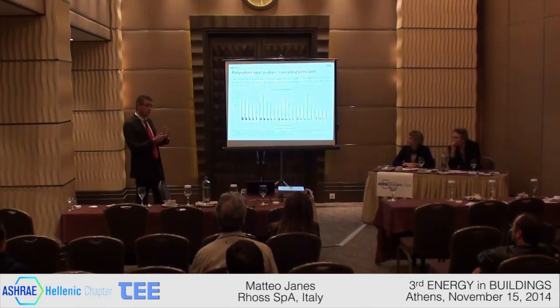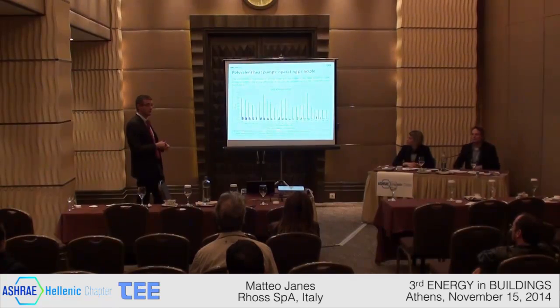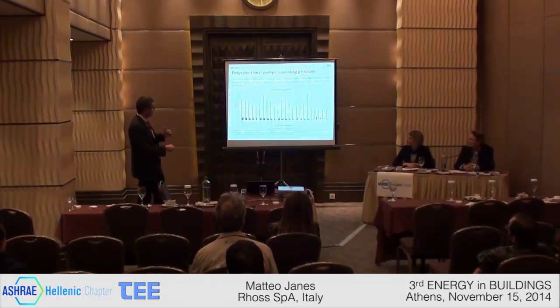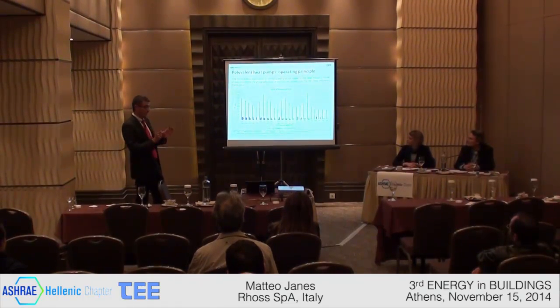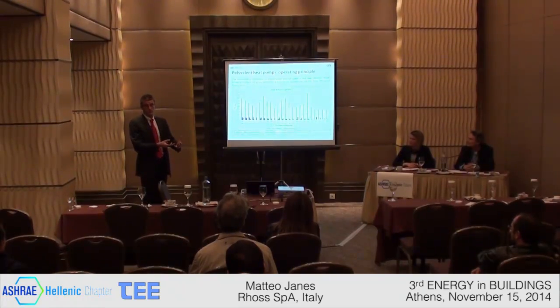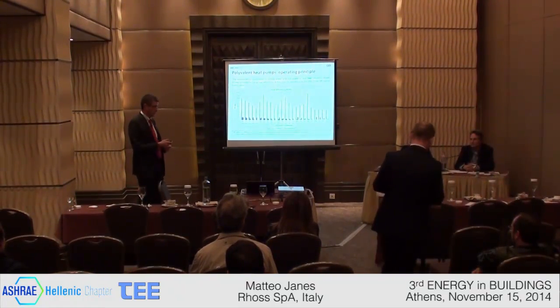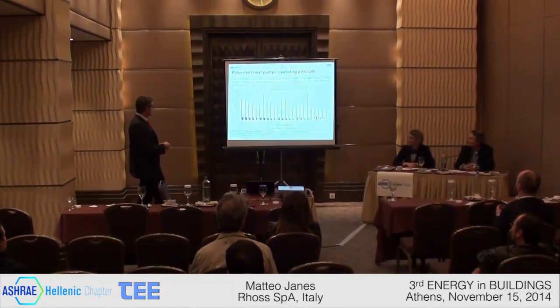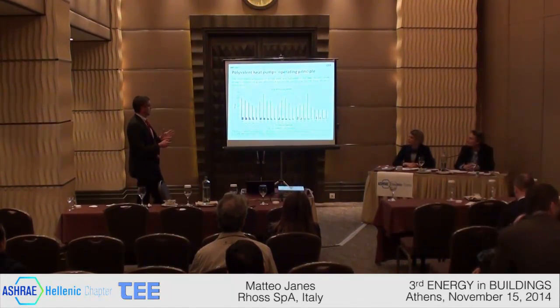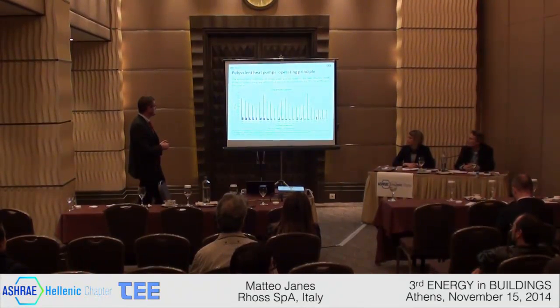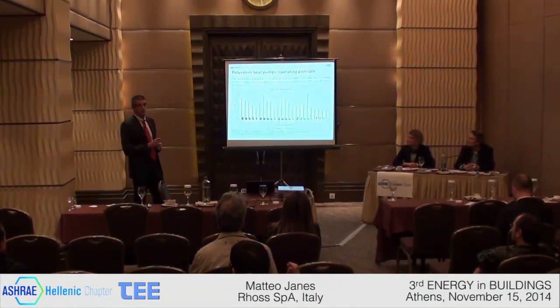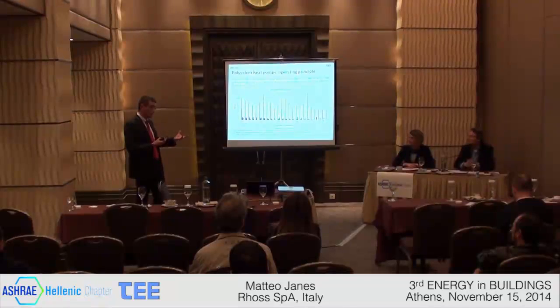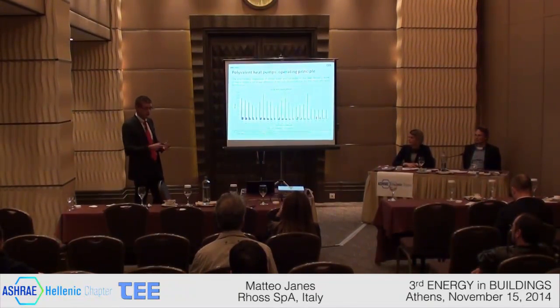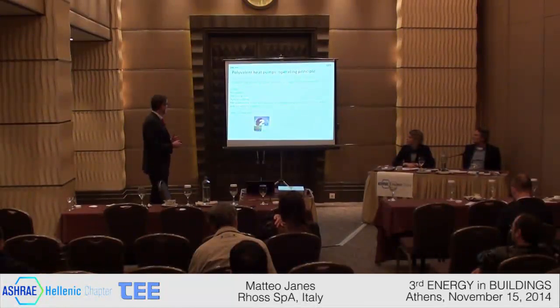The reason is that if we need more cooling than heating, then a part of the heating capacity is rejected and cannot be recovered. Or if we need more heating than cooling, it means that part of the heating capacity must come from the heat pump, and so we have to pay for that. We have to use additional energy. But in these operating conditions, TER values exceeding 9 are not uncommon. It means that we pay 1 to get 9. So we get 9 kilowatts of cooling and heating capacity with just 1 kilowatt of power input.